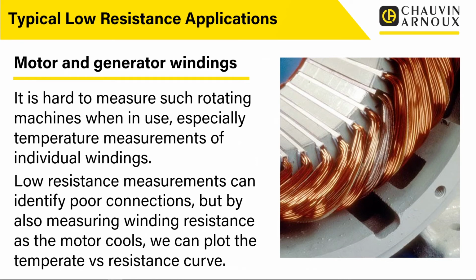But also we can look at heating effects, and this is quite a clever application, really. What they do is take winding measurements as the motor cools. We can take a cold measurement at the start. We can then run the motor for a period of time, take it apart, and as it cools, we take temperature measurements and resistance measurements, and we can plot a curve. What we can do with that curve then is sort of backtrack up the curve to see what the resistance would have been and what the temperature would have been at certain conditions. So we can see where, for example, one winding is getting a lot hotter than others. We can identify that by plotting these curves. And this is a typical application where micro-ohmmeters are used for doing these sort of checks on large motors and generators.